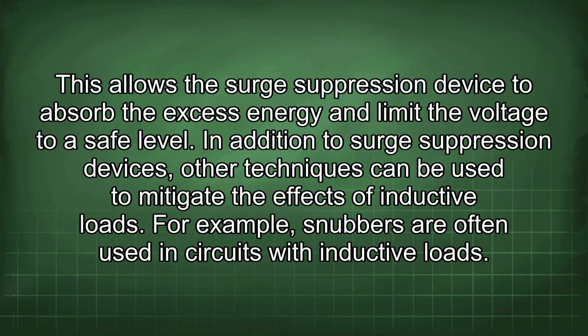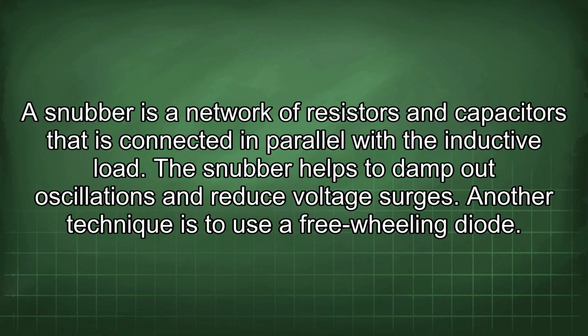In addition to surge suppression devices, other techniques can be used to mitigate the effects of inductive loads. For example, snubbers are often used in circuits with inductive loads. A snubber is a network of resistors and capacitors that is connected in parallel with the inductive load. The snubber helps to damp out oscillations and reduce voltage surges.